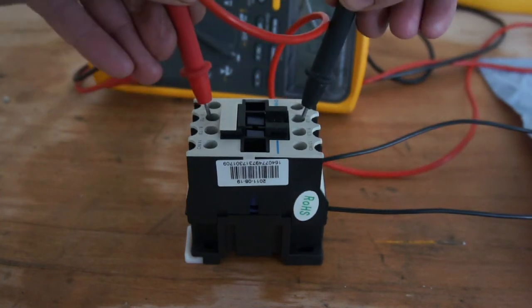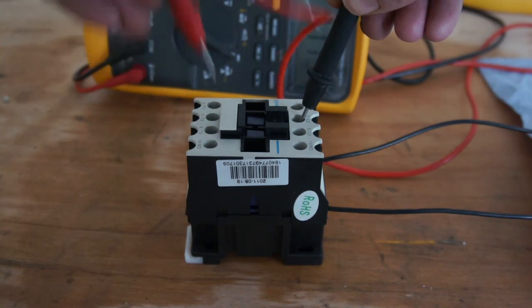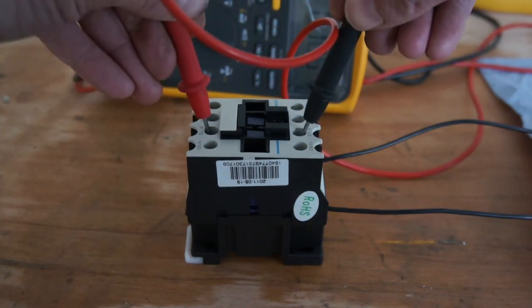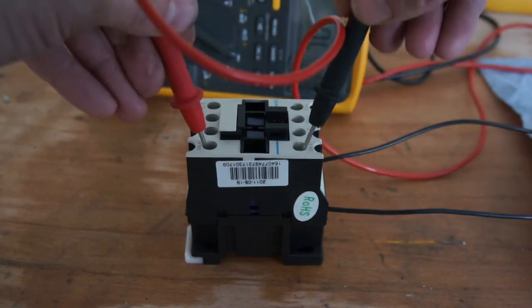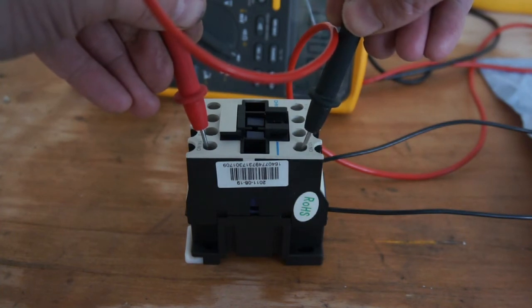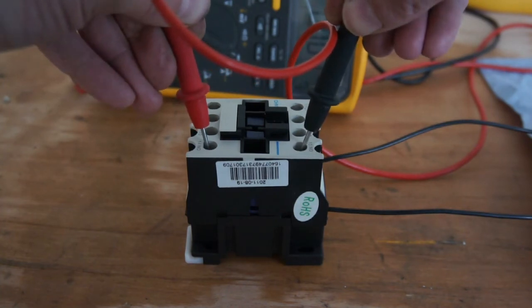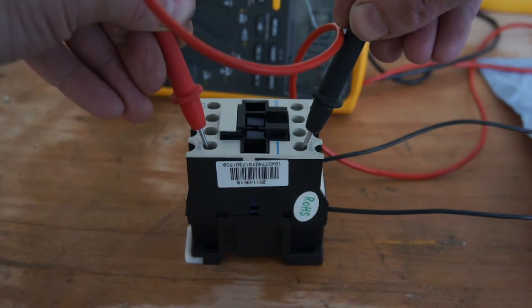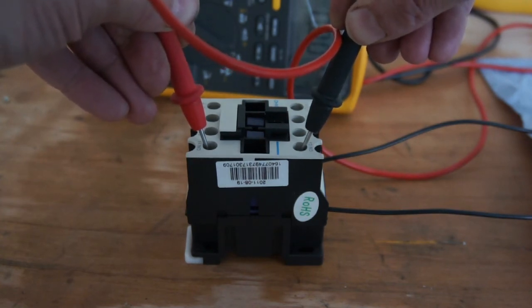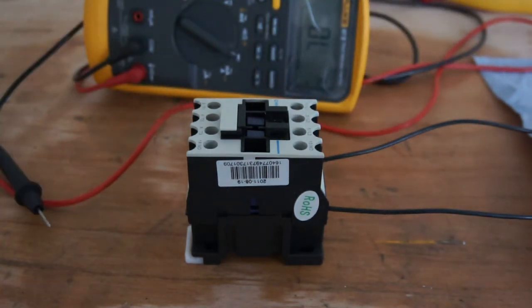All over the place. That one's better but it's showing resistance look. I'd fail that one even. Even showing 0.001 or 2 shows you've got too high resistance. Should be in the micro ohms.